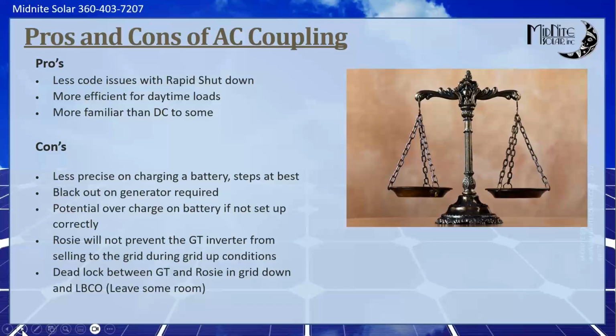And then, one of the other pros really is it is just more familiar than DC. And that may seem weird to some people, and it may not seem weird to some people. A lot of installers out there have a lot of experience doing pure grid tie. They're doing Enphase, AP systems, or the likes of that, where it is all AC wiring. That's where the work is, and starting to string together strings for DC charge controllers is something they're not very intimately familiar with, and it can make them a little uncomfortable. So rather than steering the customer away from a battery-based system, use it as an upsell and sell them an AC coupled system. That's another one of those things where AC coupling can be a retrofit, right?